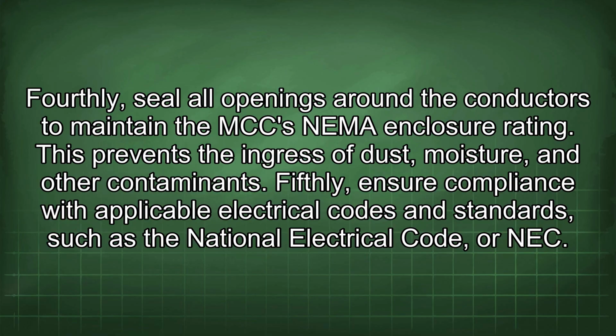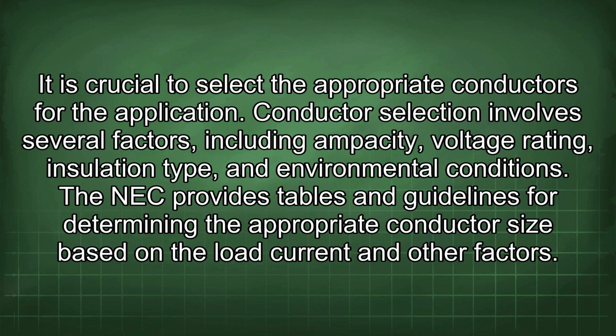Fifthly, ensure compliance with applicable electrical codes and standards such as the National Electrical Code, or NEC. It is crucial to select the appropriate conductors for the application. Conductor selection involves several factors, including ampacity, voltage rating, insulation type, and environmental conditions. The NEC provides tables and guidelines for determining the appropriate conductor size based on the load current and other factors.